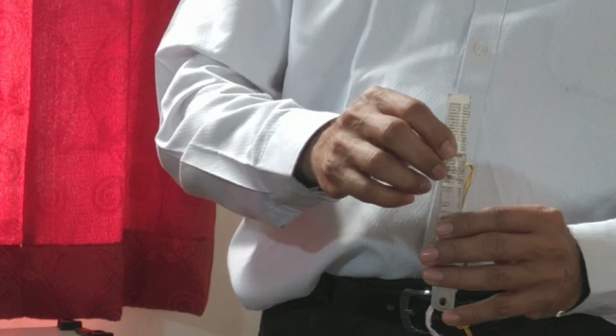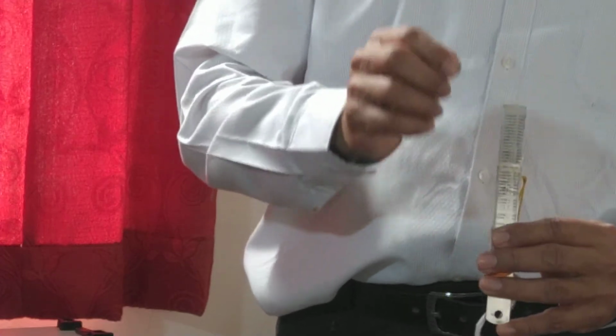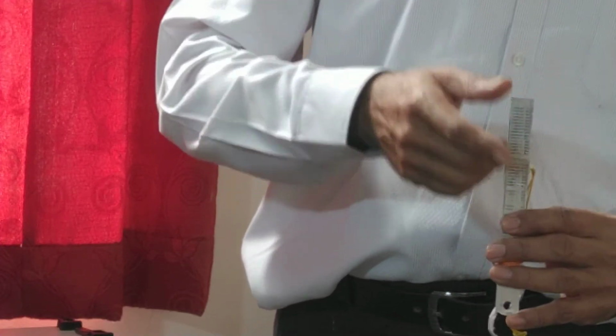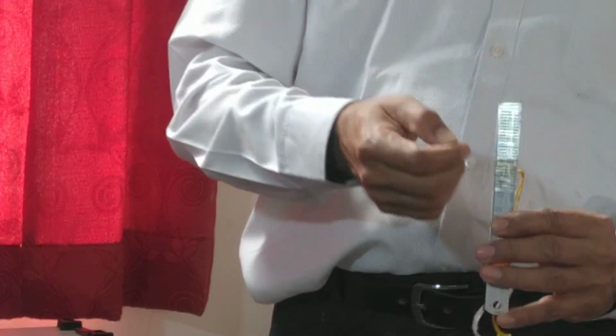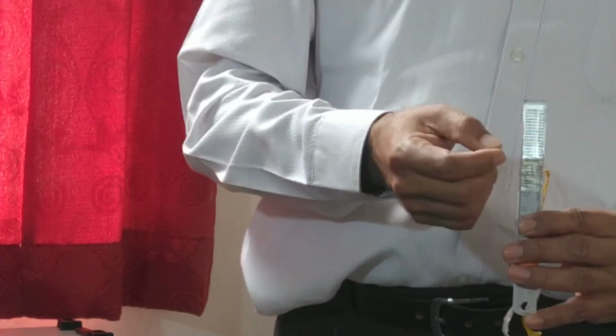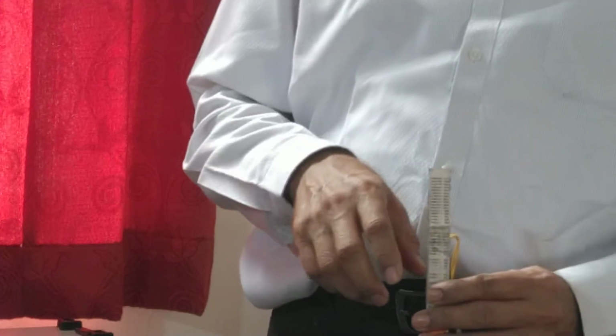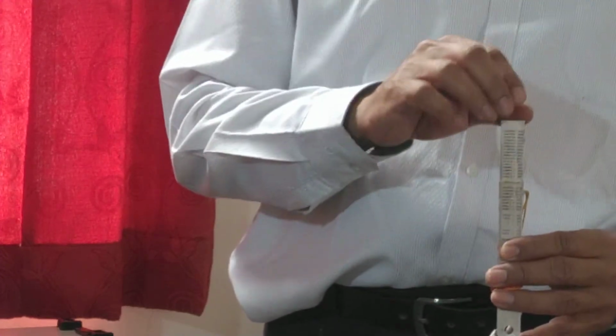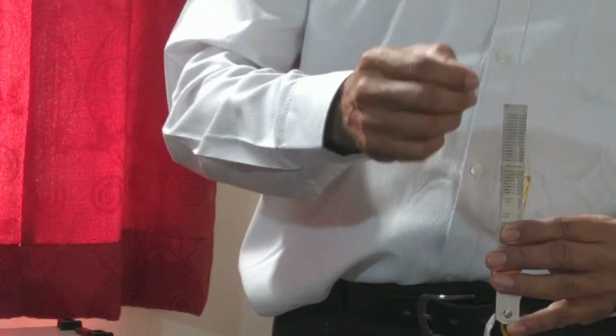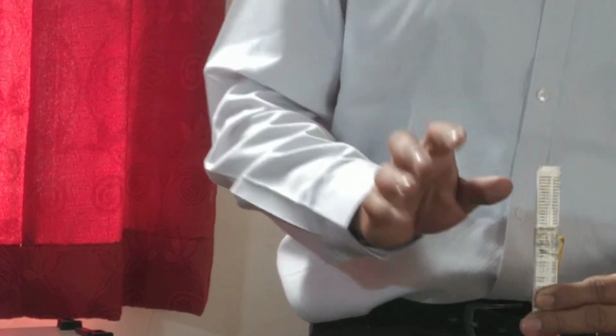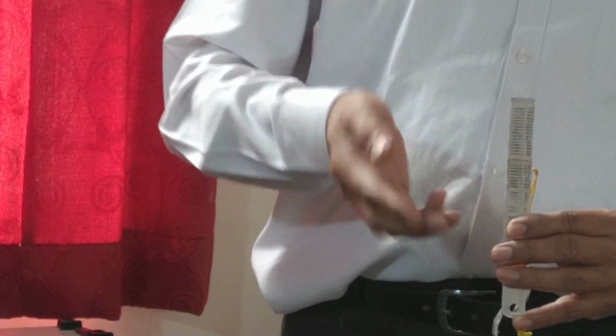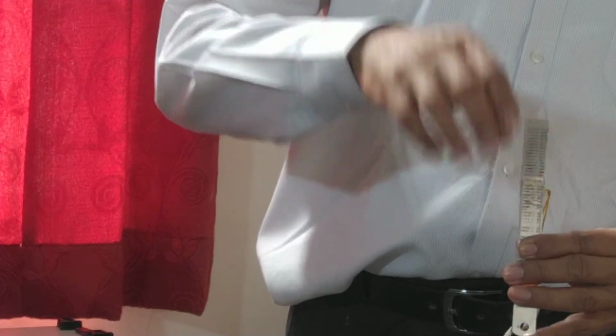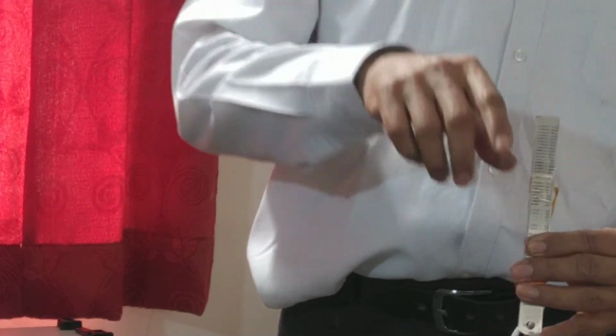To check whether the strain gauge is properly mounted or not, before mounting, the original resistance of the strain gauge is measured using a multimeter. Suppose, for example, the strain gauge has a resistance of 250 ohms. If I have done proper mounting, that resistance should not change.